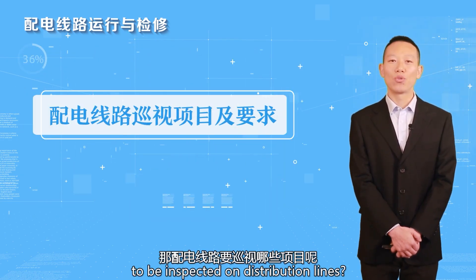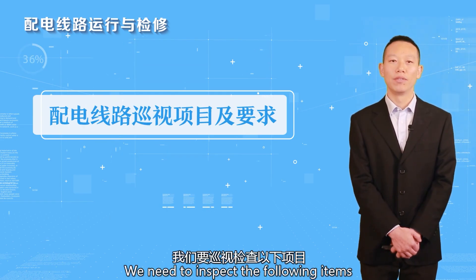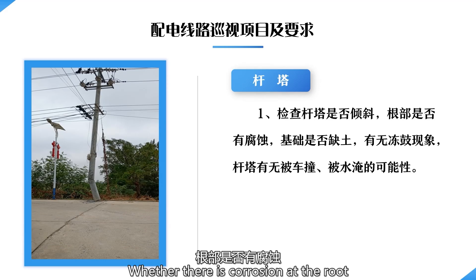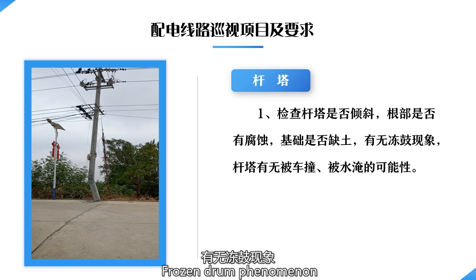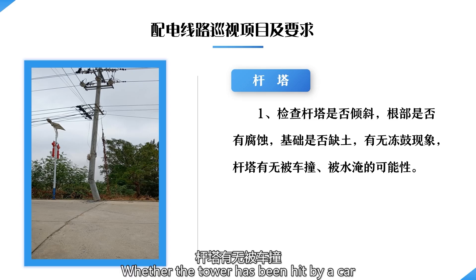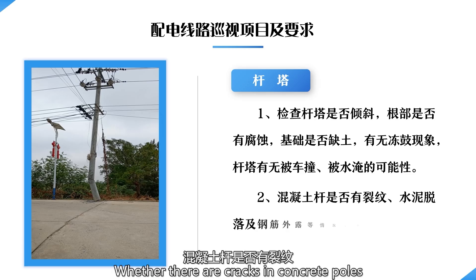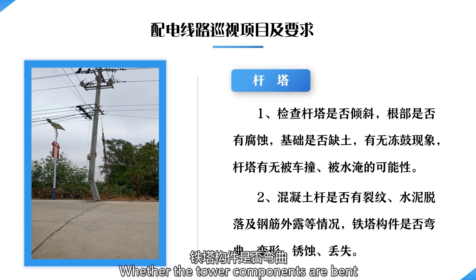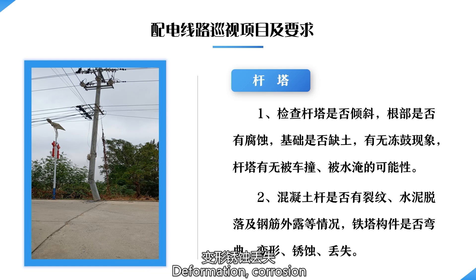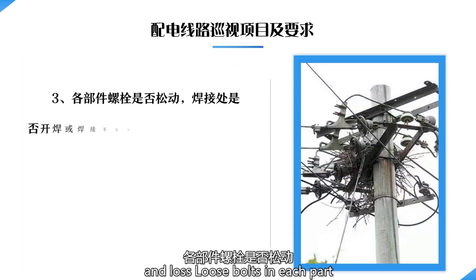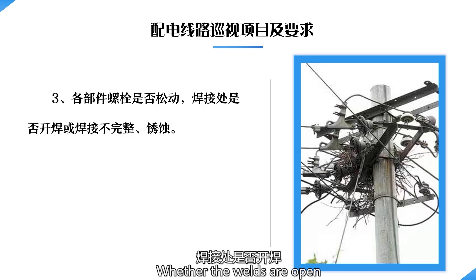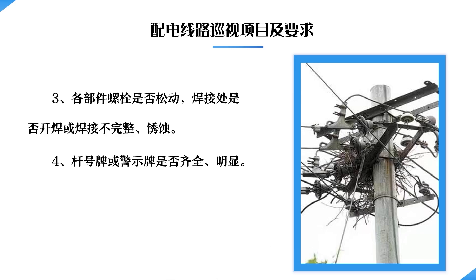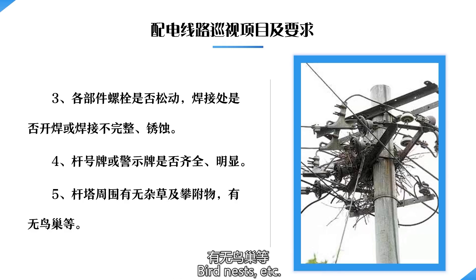Inspection items for distribution lines include: checking whether the tower is tilted, whether there is corrosion at the roots, whether the foundation lacks soil, frost heave phenomena, whether the tower has been hit by a car, possibility of flooding, whether there are cracks in concrete poles, cement peeling off and steel reinforcement exposed. Also check whether tower components are bent, deformed, or corroded, whether bolts are loose, whether welds are open or incomplete. Check whether number plates and warning signs are complete and obvious, and whether there are weeds, climbers, or bird nests around the pole tower.